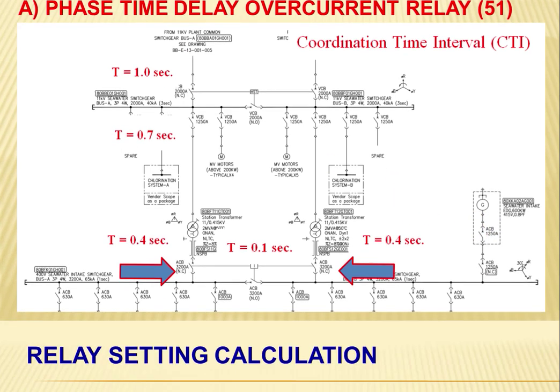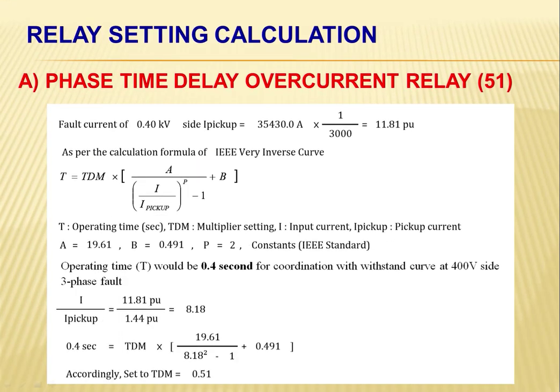Okay, so in order to solve the pickup in terms of fault current at 400 volts side, here is where the fault occurred. We're going to perform a short circuit analysis, the minimum short circuit analysis. We have this value here.